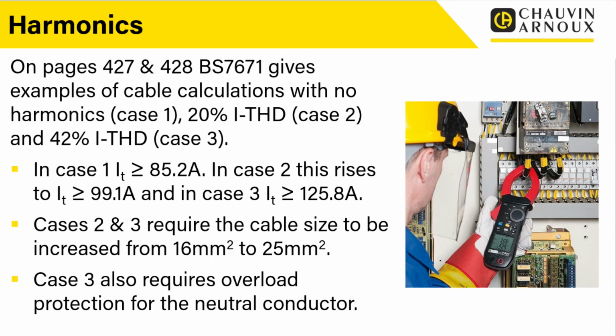Now, in both cases 2 and 3, this actually requires the cable size to be increased from a 16mm squared all the way up to a 25mm squared. Although I do think case 2 was quite borderline, it was right on the edge. But it does show that based on the harmonics that are present and what we measured in the installation, if we were doing our cable calculations correctly, it may actually increase cable sizes based on the harmonic content. And I would guarantee in a lot of cases, nobody is doing that. Nobody is actually carrying out those calculations and doing that properly.